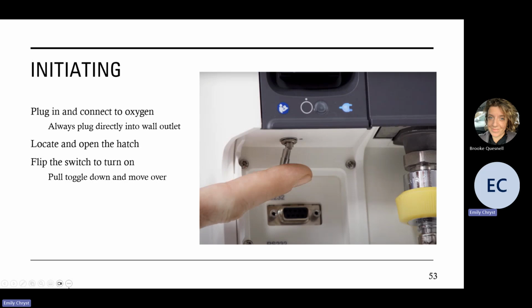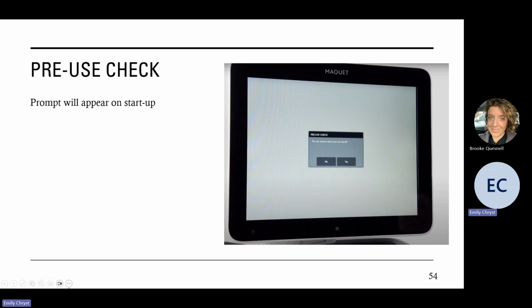So to turn it on, you're going to flip that little toggle. You do have to pull it down and move it over, but you can see it right there. And then when your machine starts, it's going to ask you to do a pre-use check. We have to do this for every single patient that goes on the ventilator. So you are going to get a prompt for this as soon as it starts up, and you're going to hit yes. Again, every single patient that goes on the ventilator needs this pre-use check.